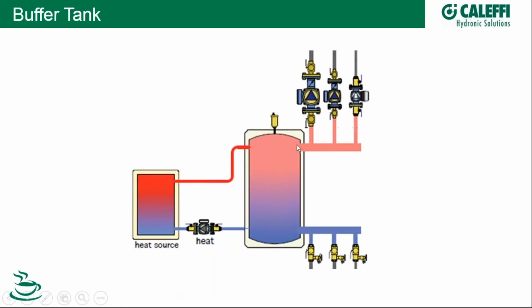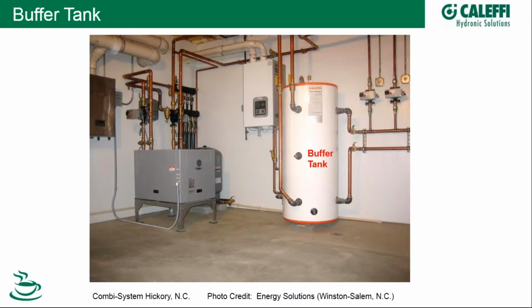So in doing an arrangement this way, you reduce the taxing wear and tear on your, say if it's your heat pump, the contactors on your compressor inside of your heat pump, or in a condensing boiler, the on-off actuations that a condensing boiler will experience. Anything, if you can minimize on-off, you're going to improve the life. And in the case of the buffer tank, increase the efficiency of the system. So here's an execution of a buffer tank. This is a job that was down in Winston-Salem from a few years back. Thanks guys for submitting this a while back.